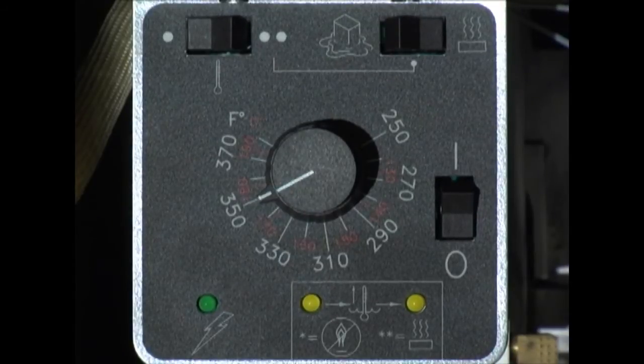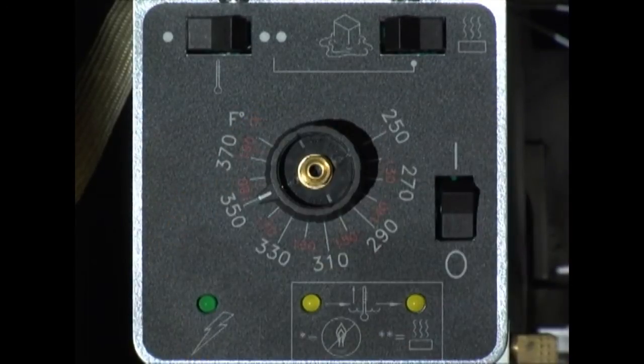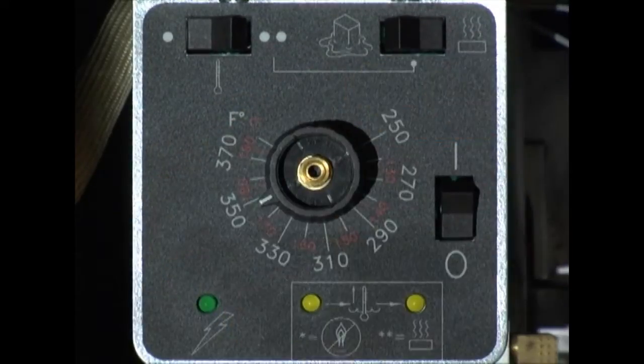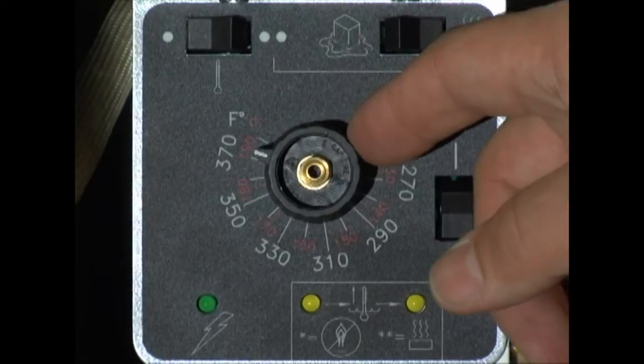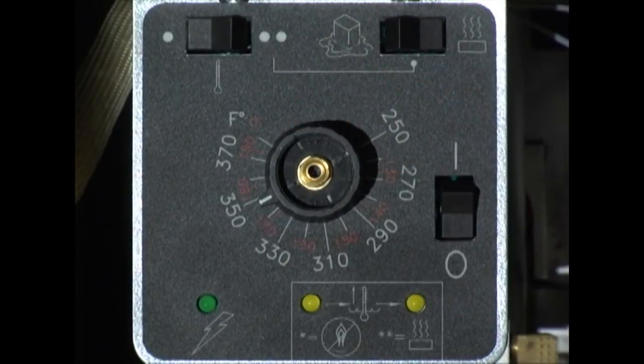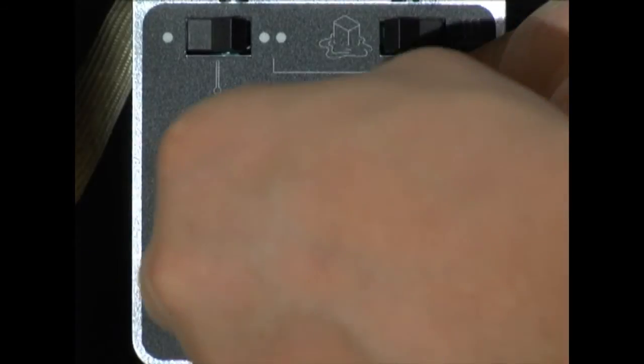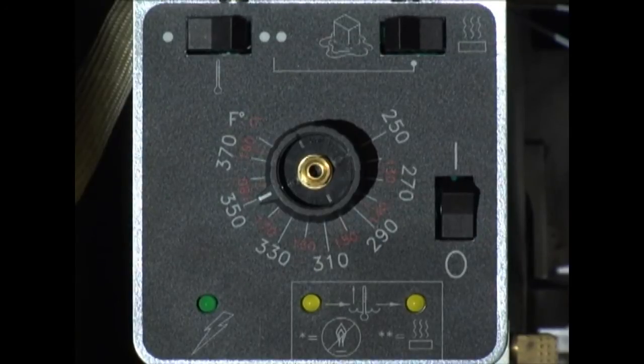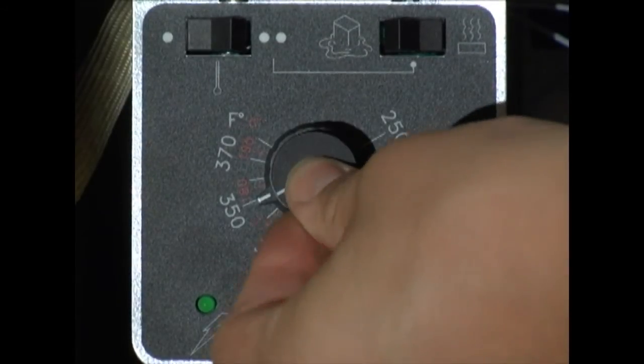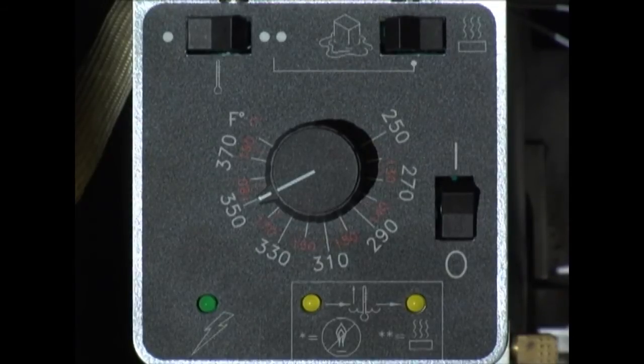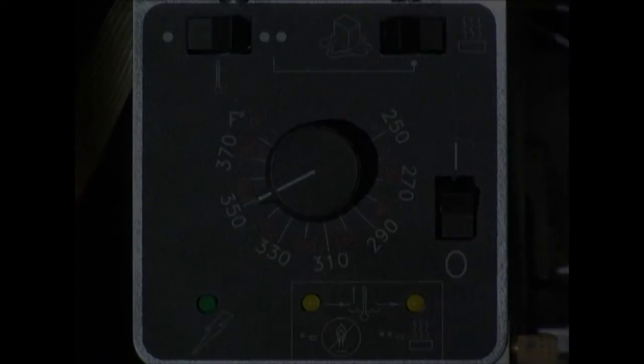If the temperature reading of your meter does not match that of the knob indicator, pry off the plastic cap from the indicator knob. Without turning the shaft, loosen the 5/16 compression nut. Align the knob indicator so it matches the reading of your meter and retighten the nut. Once finished, press the cap firmly back in place, making sure the lines on the cap and the knob are aligned. Thank you for watching this video on the solid state temperature control.